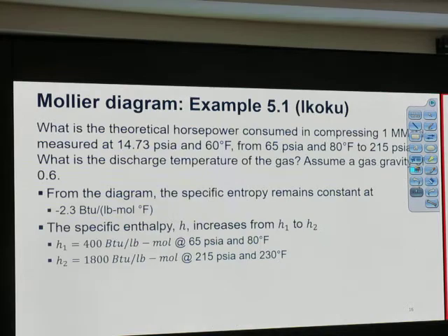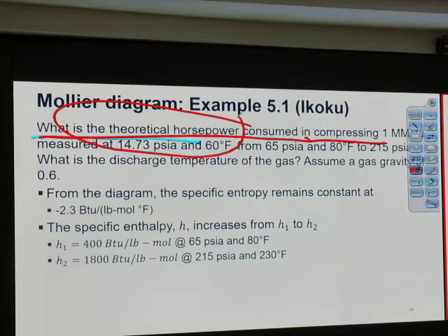So that's why in Ikoku, that's the name of the textbook, we assume what is the theoretical horsepower consumed by the compressor. Theoretical horsepower is based on constant S. You need to know that, okay? Not H. If you do constant H, that's wrong.